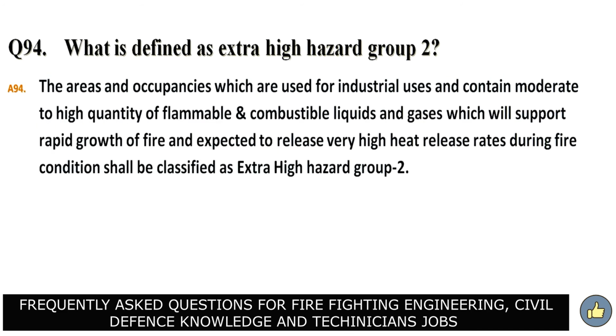What is defined as extra high hazard group 2? Answer. The areas and occupancies which are used for industrial uses and contain moderate to high quantity of flammable and combustible liquids and gases which will support rapid growth of fire and are expected to release very high heat release rate during fire conditions shall be classified as extra high hazard group 2.